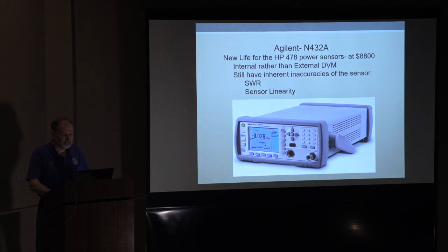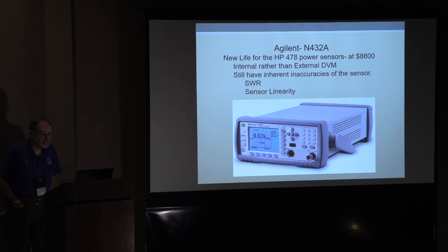Okay, next. There we go. This is an interesting story because when they came out with new sensors, guys said, well, why don't you just make a better 432? That way it'll be traceable. Well, HP finally did. This is an elaborate power meter. It has a 6.5-digit digital voltmeter inside that measures directly from the sensor to get better accuracy in the measurement.